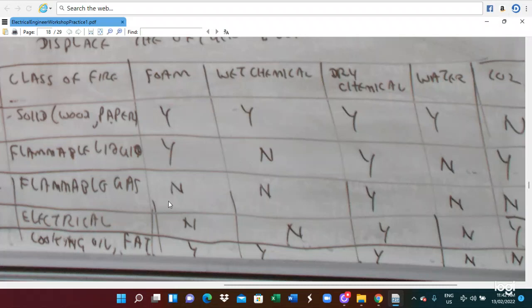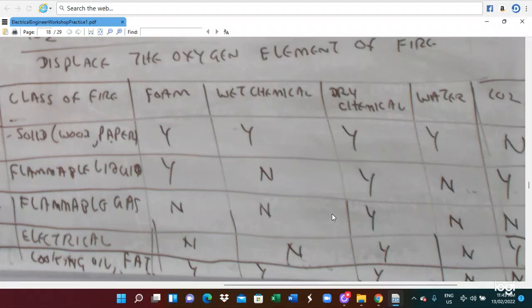Flammable gas, you cannot use foam, you cannot use wet chemical, you can utilize dry chemical, you cannot use water, you cannot use carbon dioxide. Electrical fire, you cannot use foam, you cannot use wet chemical, you can utilize dry chemical, you cannot use water, you can use carbon dioxide. Cooking oil fire, you can use foam, wet chemical, dry chemical, but you can't use water and you can't use carbon dioxide. This is how to use the appropriate kind of fire extinguisher for the type of fire.